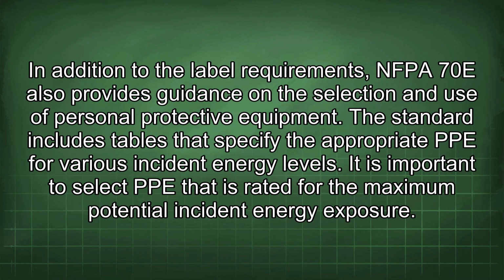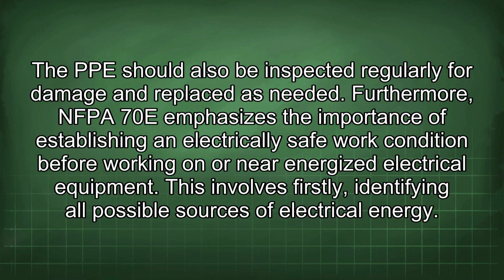injuries. In addition to the label requirements, NFPA 70E also provides guidance on the selection and use of personal protective equipment. The standard includes tables that specify the appropriate PPE for various incident energy levels. It is important to select PPE that is rated for the maximum potential incident energy exposure. The PPE should also be inspected regularly for damage and replaced as needed.